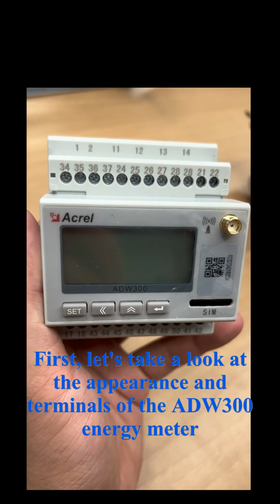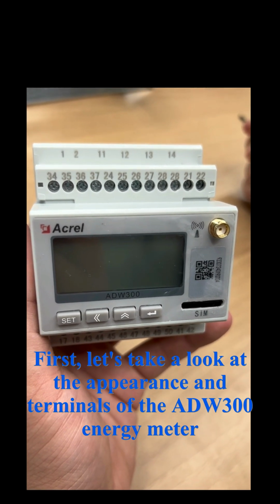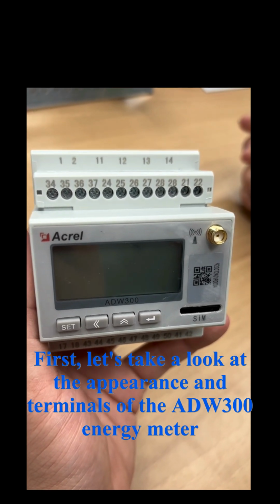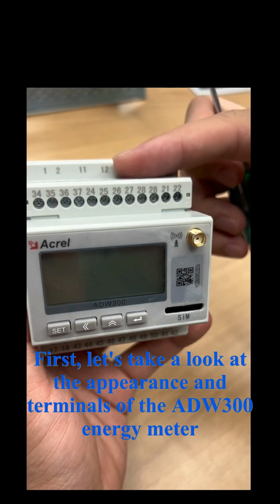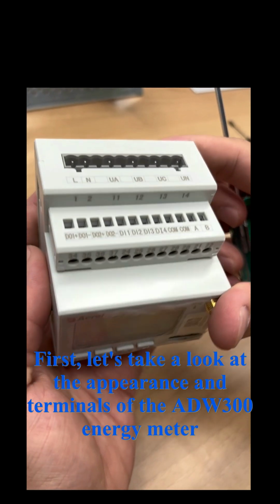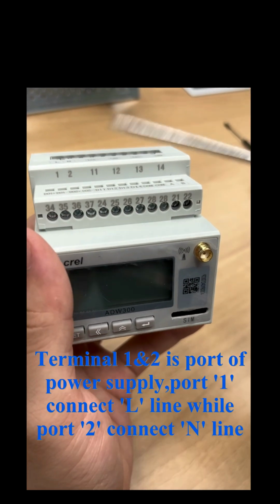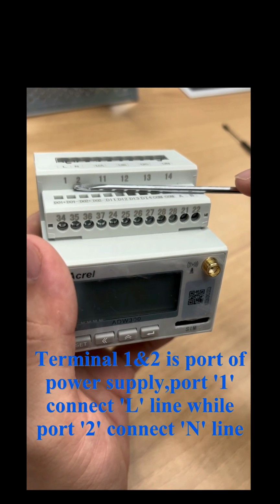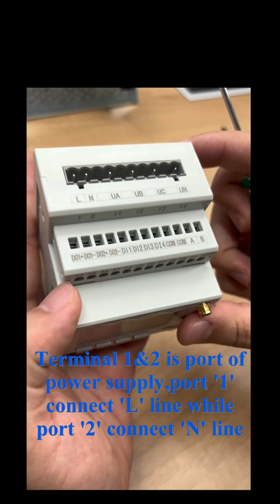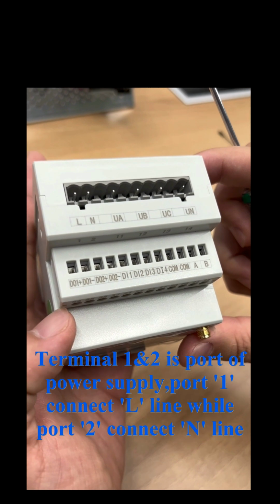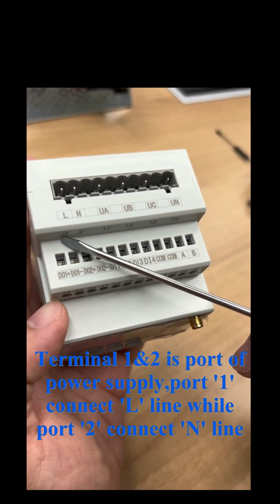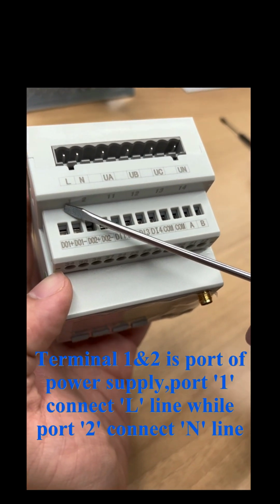First, let's take a look at the appearance and terminals of the ADW300 energy meter. Terminals 1 and 2 are the power supply ports. Port 1 connects to the L line, while port 2 connects to the N line.